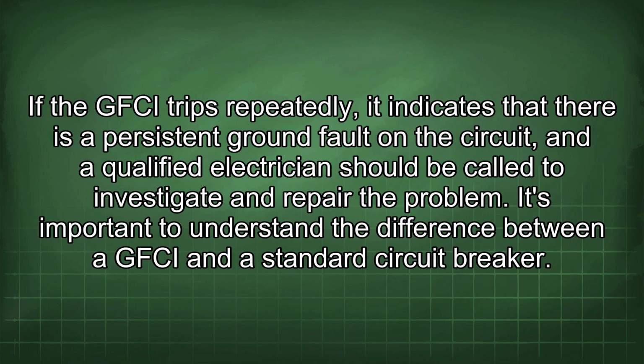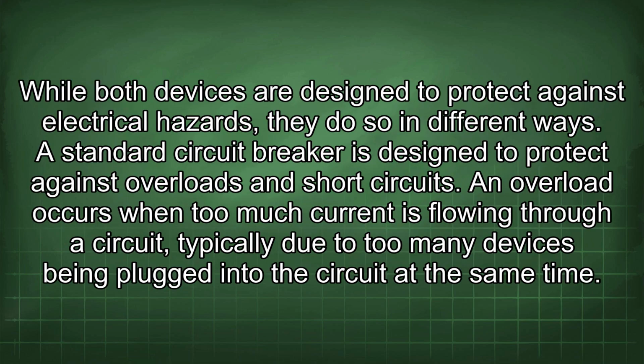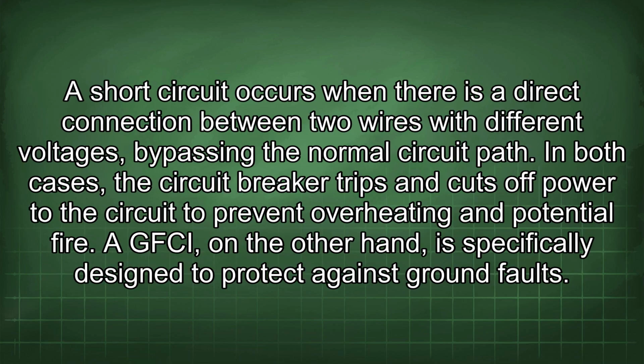It's important to understand the difference between a GFCI and a standard circuit breaker. While both devices are designed to protect against electrical hazards, they do so in different ways. A standard circuit breaker is designed to protect against overloads and short circuits. An overload occurs when too much current is flowing through a circuit, typically due to too many devices being plugged into the circuit at the same time. A short circuit occurs when there is a direct connection between 2 wires with different voltages, bypassing the normal circuit path.